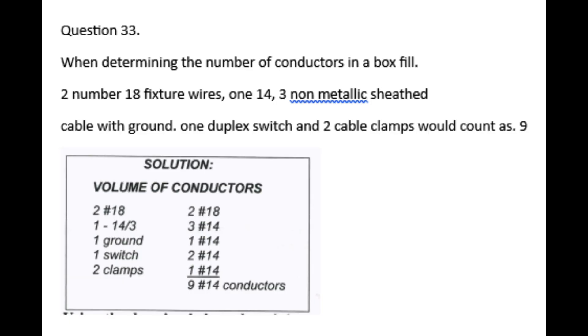Question 33: When determining the number of conductors in a box fill — 2 number 18 fixture wires, 1 number 14, 3 non-metallic sheathed cable with ground, 1 duplex switch, and 2 cable clamps — the total count is 9 conductors.